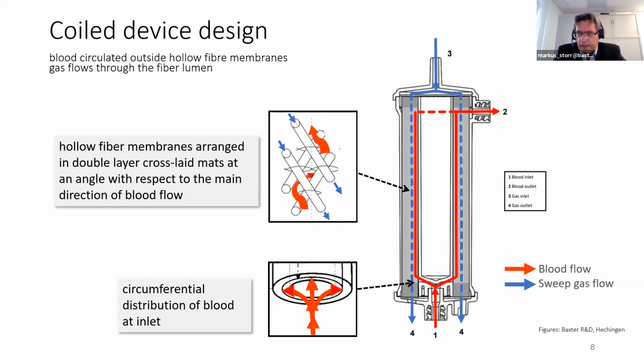We see that in this configuration, where the blood is circumferentially distributed at the inlet compartment, the blood is forced partly around and partly along the cylindrical membranes. And depending on the membrane angle with respect to the direction of the blood flow, and the membrane diameter, packing density, and so on, such a flow pattern can generate considerable mixing. And as indicated by the blue arrows, the sweep gas, or air, as most commonly is used, flows in the capillary lumen on the basis of the countercurrent flow principle.